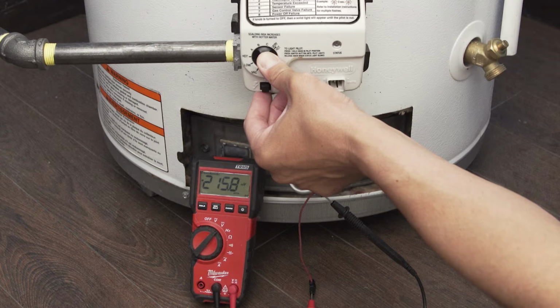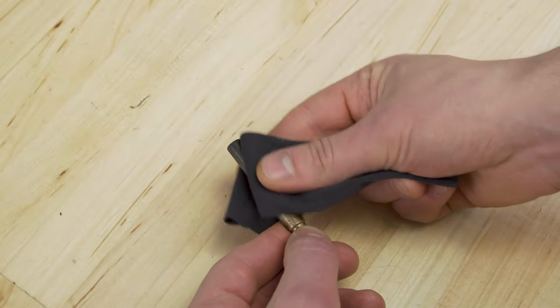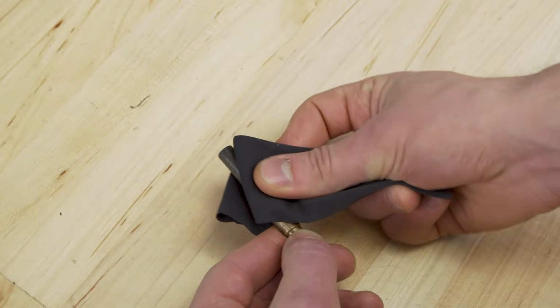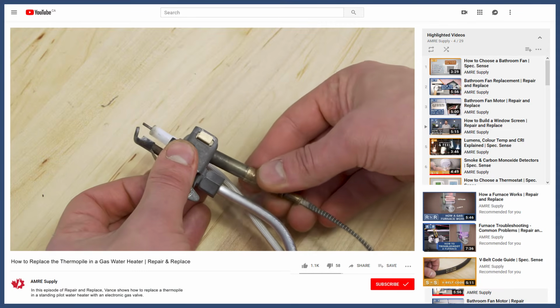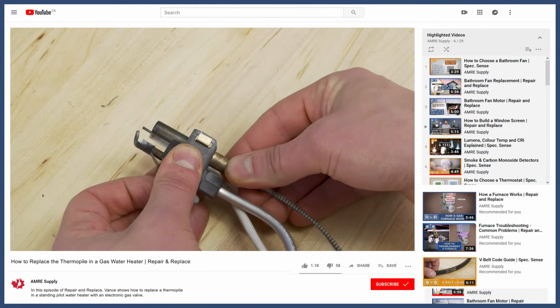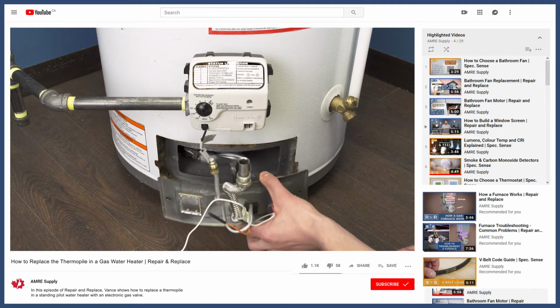If the multimeter reads under 400 millivolts, then the pilot might have trouble staying lit. Over time, a buildup of carbon will act as an insulator and will reduce the voltage. One solution is to clean it, but in a lot of cases, it's best to install a new thermopile. You can see how to do this in the video linked below.